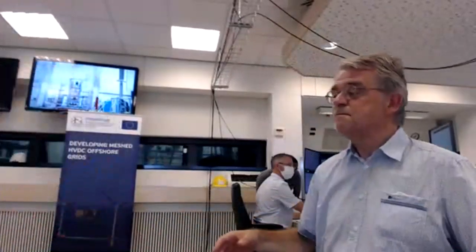Please take a chair. What is the meaning of VARC? So VARC stands for voltage source converter assisted resonant current injection breaker. And we feel that the use of a voltage source converter is very important in terms of the advantages you get. So that's why we want to stress it, and that's why we call it a VARC. But as you say, it's conceptually very similar to an active current injection breaker.